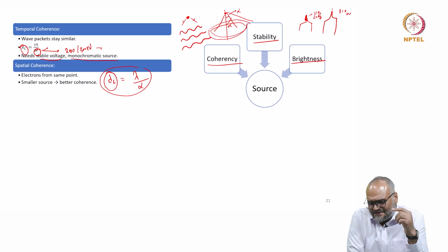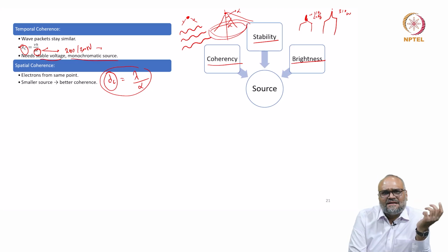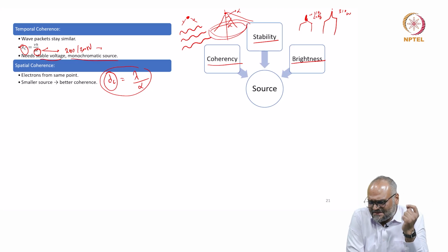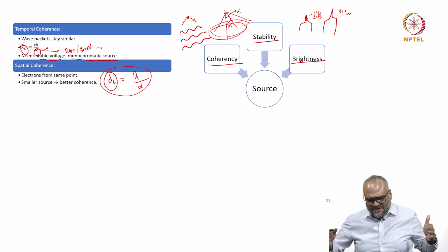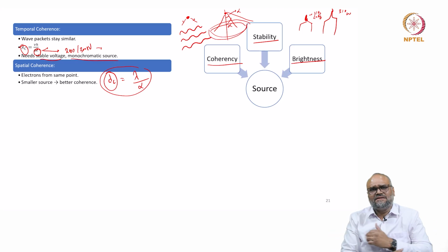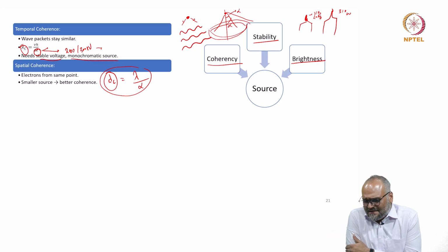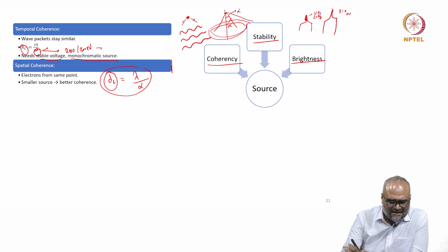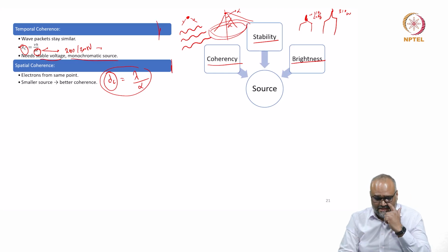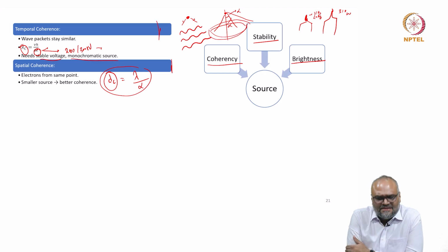Now if I take a step back and recollect the construction of a field emission gun, when the point source is extremely fine, I would have a much more spatially coherent image formed beyond the field emitter. So within a field emission gun, my spatial and also temporal coherence is significantly better than I have from a lanthanum hexaboride filament in a thermionic emitter.